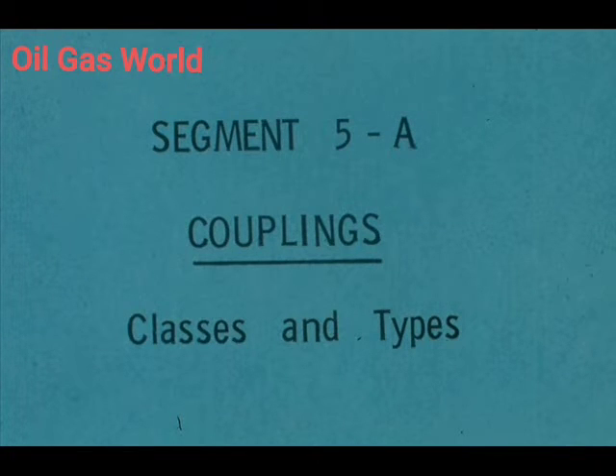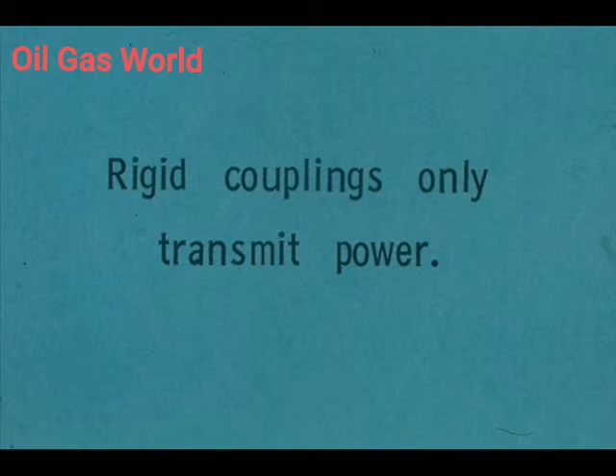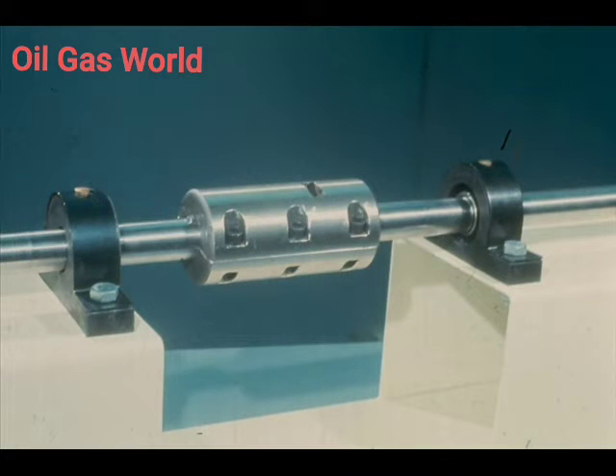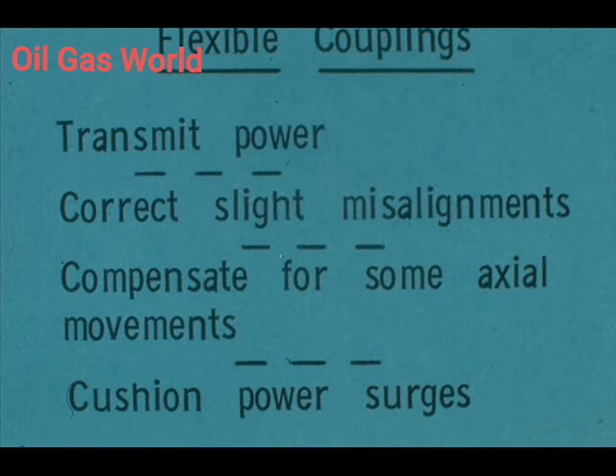There are two basic classifications of couplings that we will deal with in this course: the rigid and flexible classes. The rigid couplings are the simpler of the two, generally used in applications where transmitting power from one machine to another is the only concern — only expected to lock two shafts together, making them operate as a single shaft. The flexible couplings also transmit power but are designed to fulfill other requirements: correcting misalignments, compensating for axial movement, and cushioning power surges.